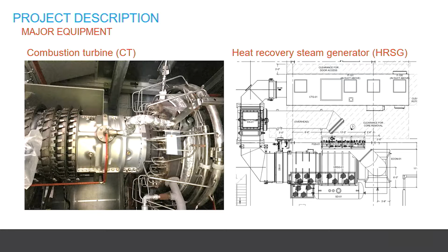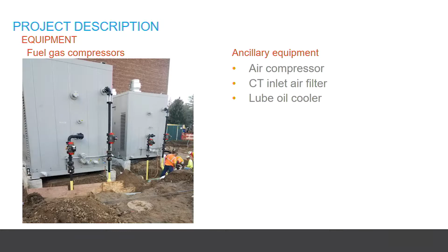They also added the fuel gas compressors. These are 100% each, so fully redundant fuel gas compressors. The Taurus 70's gas pressure requirements were more than what could be provided by the utility, so they added the gas compressors. And then also a new air compressor, inlet air filter, and lube oil cooler.